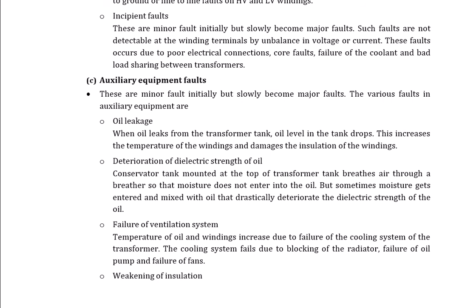Next, deterioration of dielectric strength of oil. By the aging effect, if the dielectric strength of oil deteriorates, then it will again create a problem. The conservator tank mounted at the top of the transformer tank breathes air through a breather so that moisture does not enter the oil, but sometimes moisture gets in and mixes with the oil, which drastically deteriorates the dielectric strength of the oil.